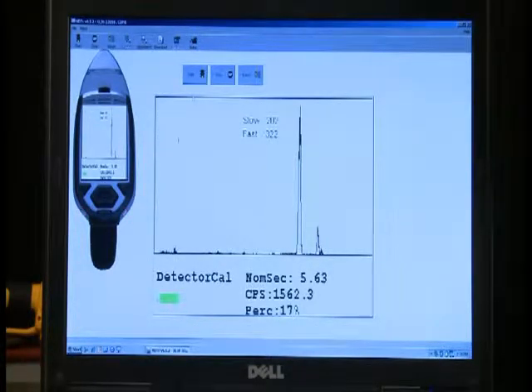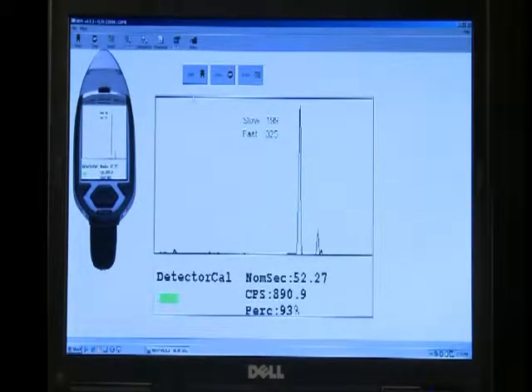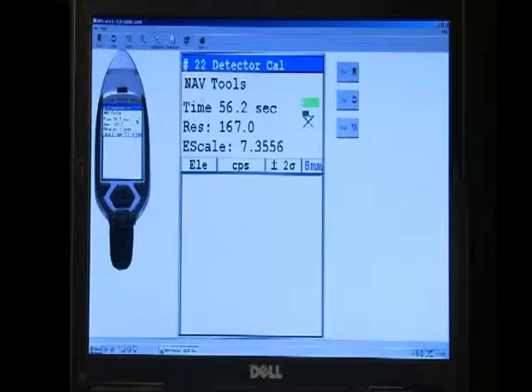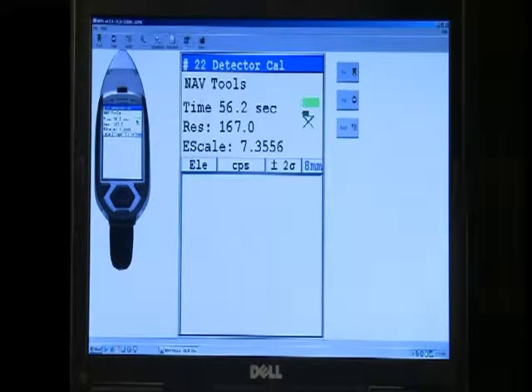You may want to pause the DVD until your calibration is complete. It is important that you are careful not to place your instrument near a CRT device, like a TV or a computer monitor, or any other known source of EMF emission during the detector calibration process. You'll also want to avoid any source of loud noise or vibration. We do recommend that you place your instrument in a quiet place so that it is not disturbed during the calibration process. During the detector calibration, the analyzer will display this screen. At the conclusion of the detector calibration, the analyzer will show the results of the calibration as we see here.